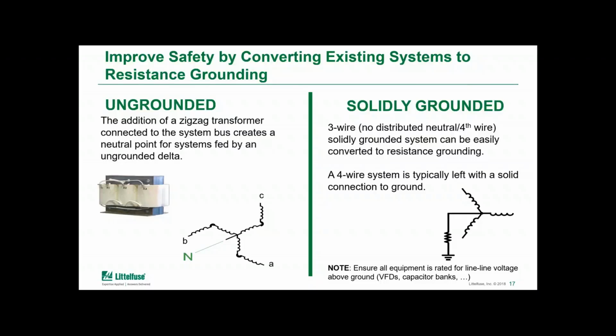It is important, though, to make sure that equipment like capacitor banks, filters, and surge arresters are rated for line-to-line voltages when you do this. On a resistance grounded system, during a ground fault condition, those unfaulted phases do rise to line voltage when the fault is present. So that's the reason for ensuring these other devices are fully rated.